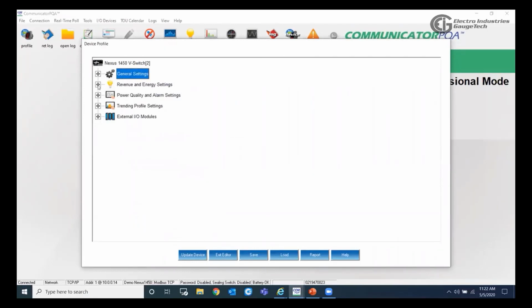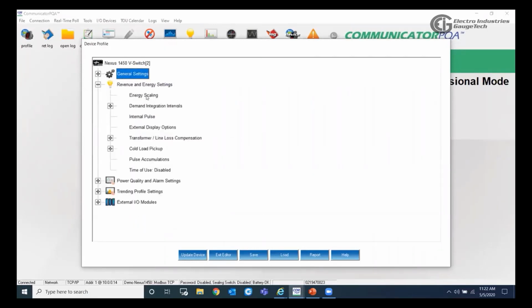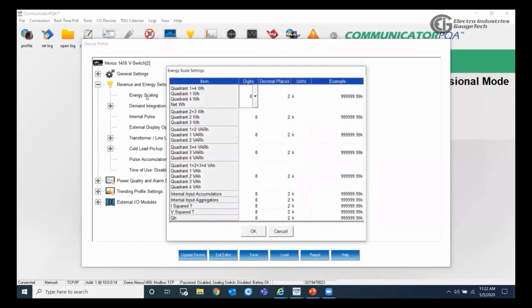After the general settings, we have the revenue and energy settings. This is where we can set the energy scaling. If I click on this one, you will see that we have all the different kinds of energy types. And this is where we can set how many digits we want to use for that accumulator. For example, the default is 8 digits, with 2 after the decimal. And the unit, is it kilo or mega or just a unit? According to what we choose here, the example will tell us how it will look. For example, if I choose 9, just 1 after the decimal, and mega, we would be looking at this accumulator. And this will tell us when it would roll over.